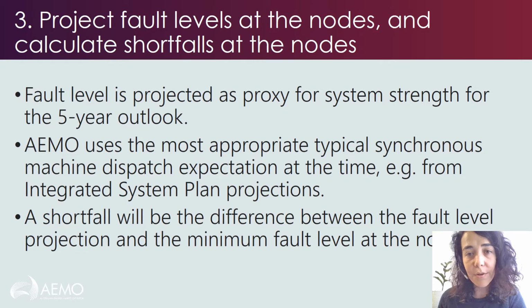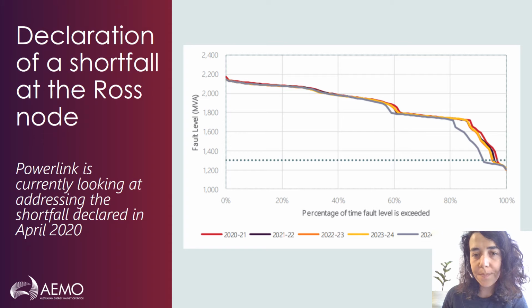We use fault level as a proxy for system strength, and we look at the 5-year outlook. We take what is our best expectation at a particular time for dispatch of synchronous machines, and we often choose to take that from our integrated system plan projections, although sometimes we update them with the latest information, for example, from the modelling from the electricity statement of opportunities. And then we do an assessment to consider whether we see a shortfall between the projected amount of fault level contribution from plant that we consider will be online and dispatching, and the minimum fault level that was already calculated for each of the nodes in the previous stage.